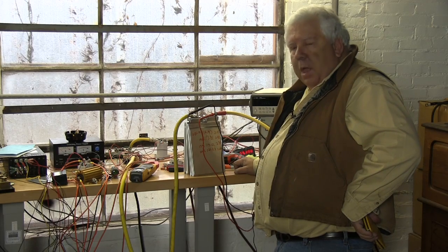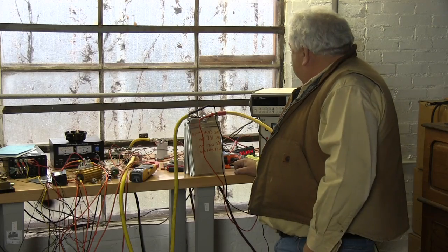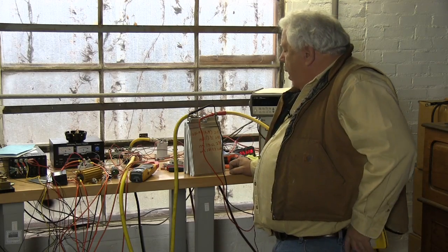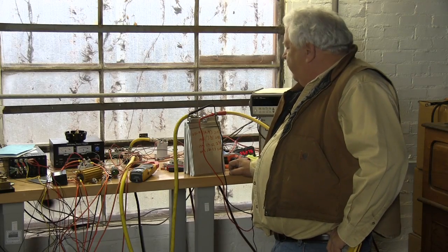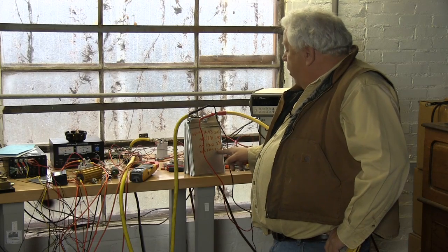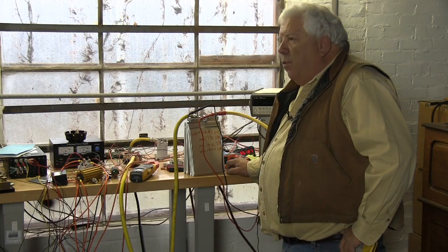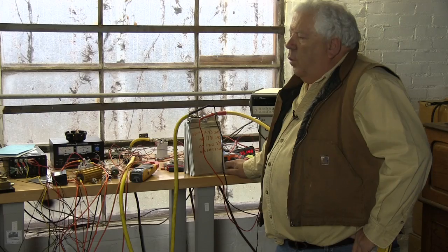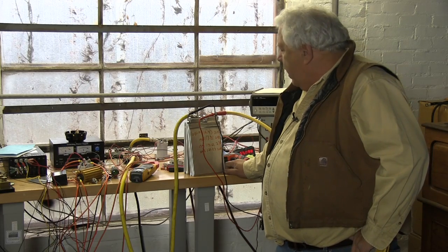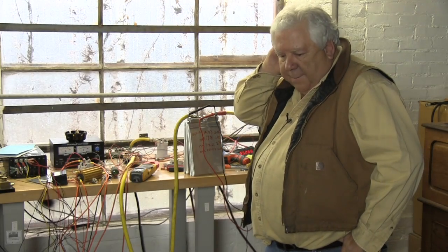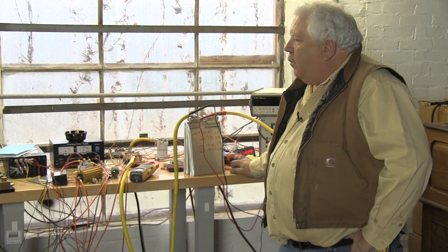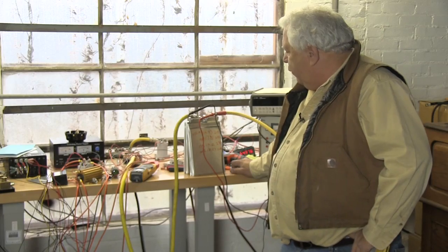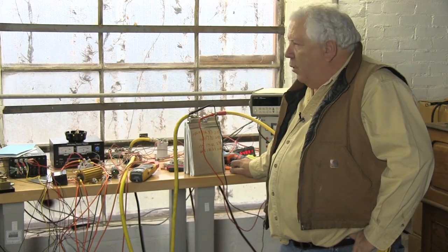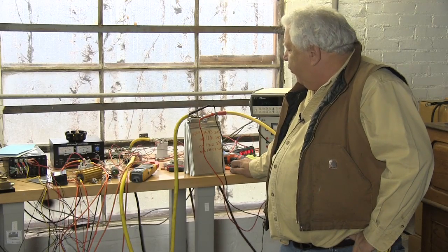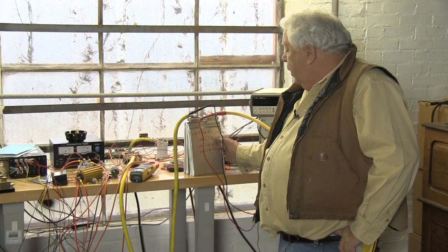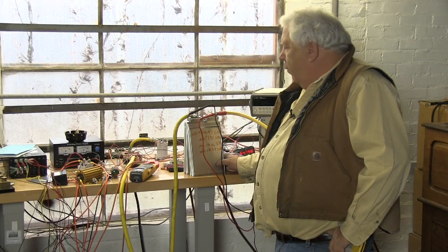From what I see, we'll continue using 2.5 volts as the low-side cutoff for these A123 cells. On charging, we got up to 3.65 volts at just about an amp hour shy of our 2-volt discharge level, with current diminished to 6 amperes, or 0.05C — the normal Thunder Sky variables we use, and they work very well for these A123s. We won't charge them any higher than that; we'll use 3.65 per cell, maybe even 3.5, and in all cases call 2.50 volts the cutoff.